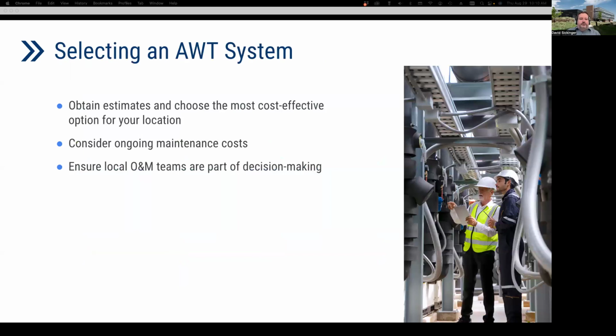When selecting an AWT system, of course, you want to obtain estimates and choose the most cost-effective option for your location. City water quality used for makeup can impact performance. Locations with excessively hard water, high pH, or high total dissolved solids typically use more water treatment chemicals, and will have the greatest opportunity for savings. Consider ongoing maintenance costs when selecting an AWT system. There are a few of these technologies that significantly reduce the amount of water treatment chemicals used. You can look into whether or not service contracts are structured to realize these chemical savings. And then ensure the local O&M teams are part of the decision making. Again, just reemphasizing that most of these systems rely on proprietary technology offered by individual vendors. Next slide, please.